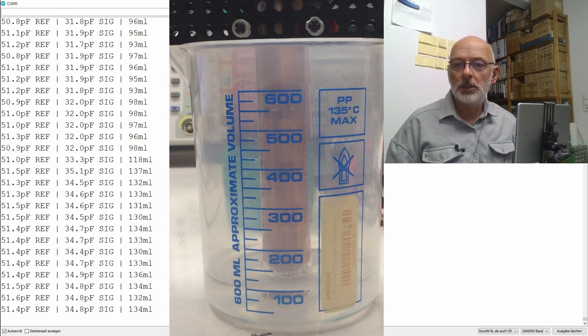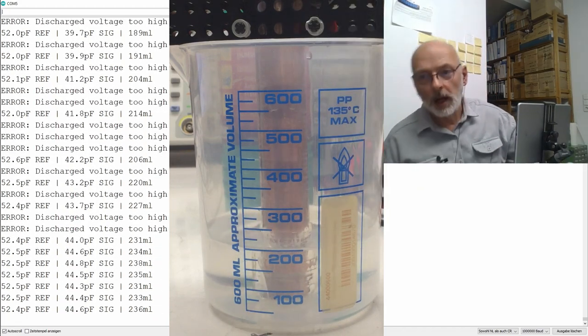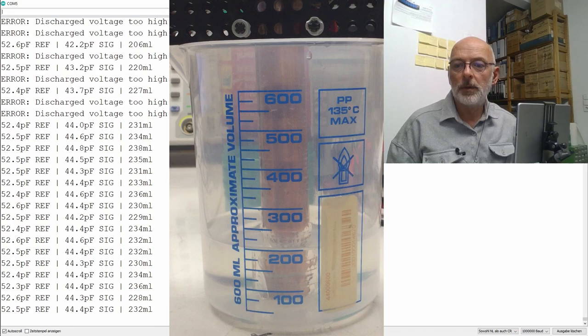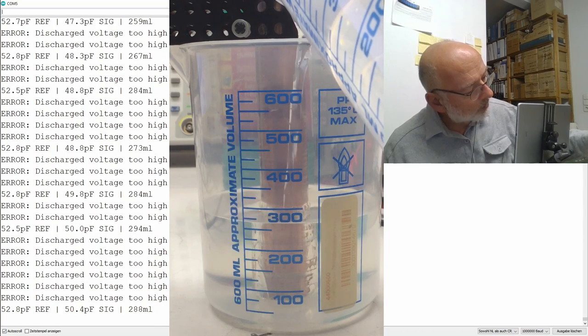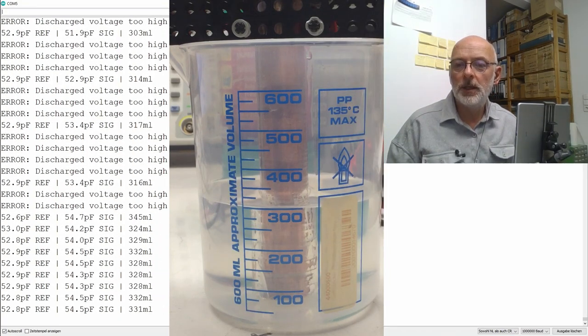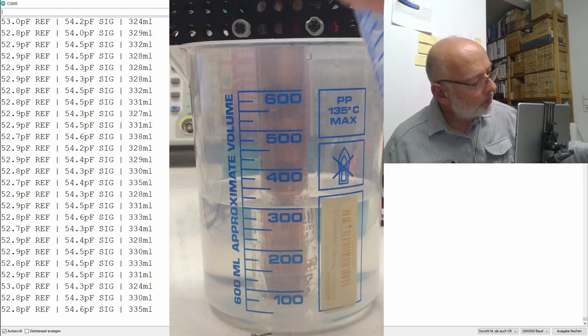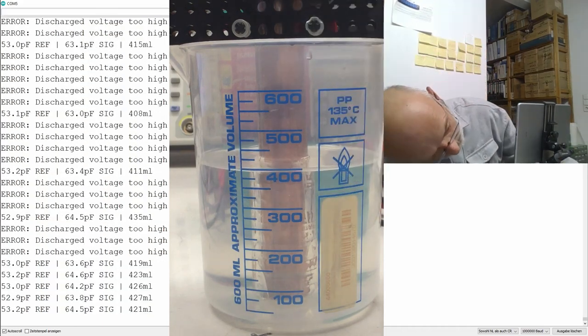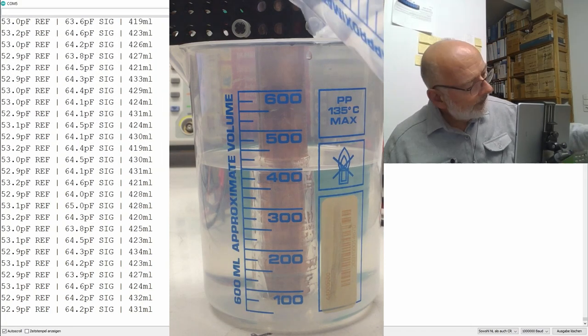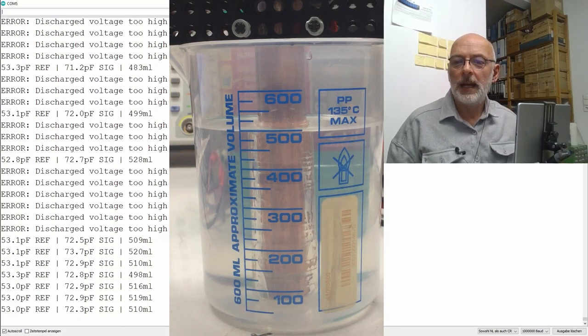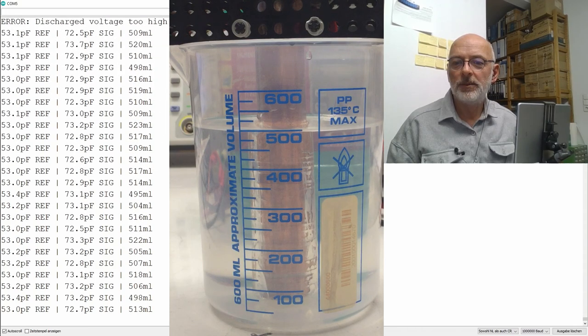We are low as expected. At 100 milliliters, we are measuring let's say 130. At 200, we are measuring 230. We're still within 5% of full scale, so that's not that bad. A little over 300, we are measuring 330. That doesn't look too bad, does it?